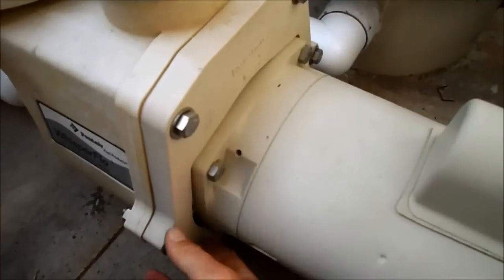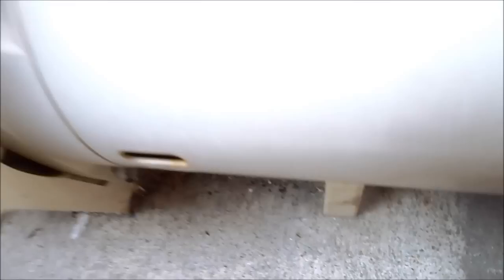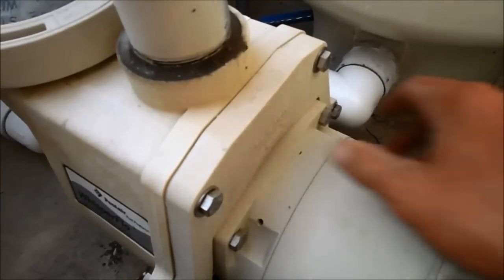All you have to do is take these six bolts — there's one, two, three, four, five, and six all around this — and the motor should slide right out of the pump. Sometimes they're bolted down to the ground, so check to make sure. Remove those bolts and this thing pulls out, and I'll show you what a diffuser and an impeller look like.